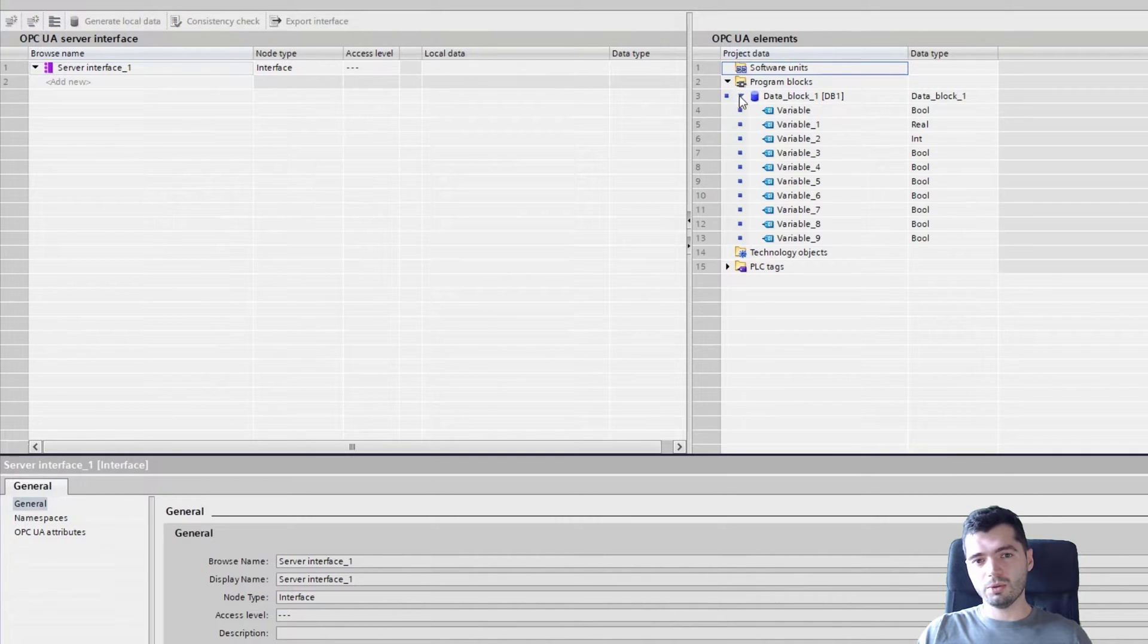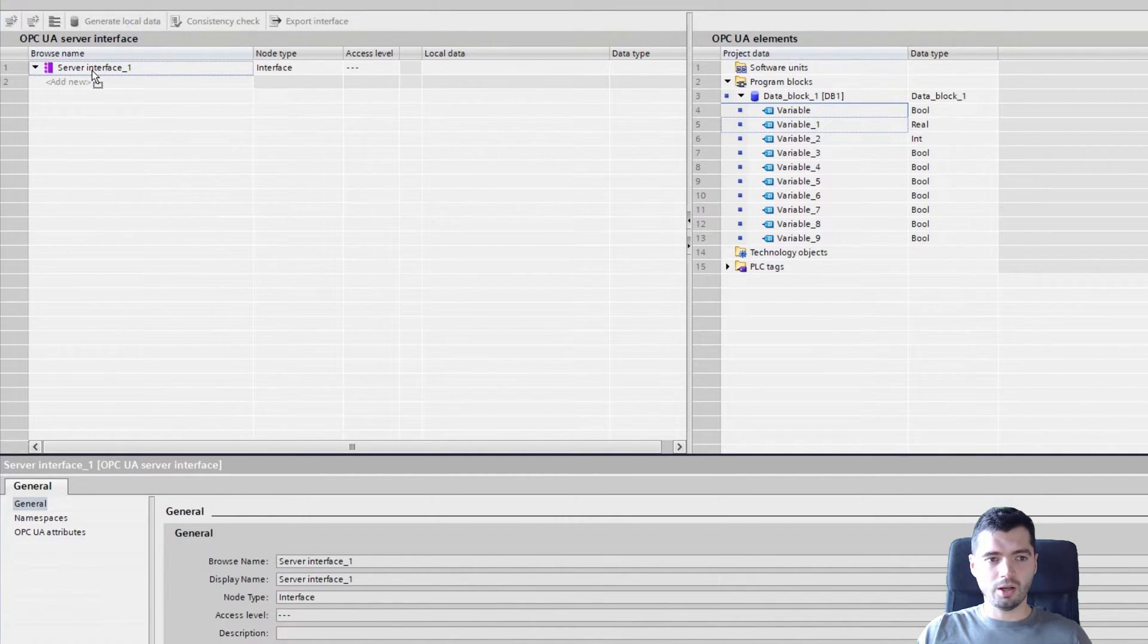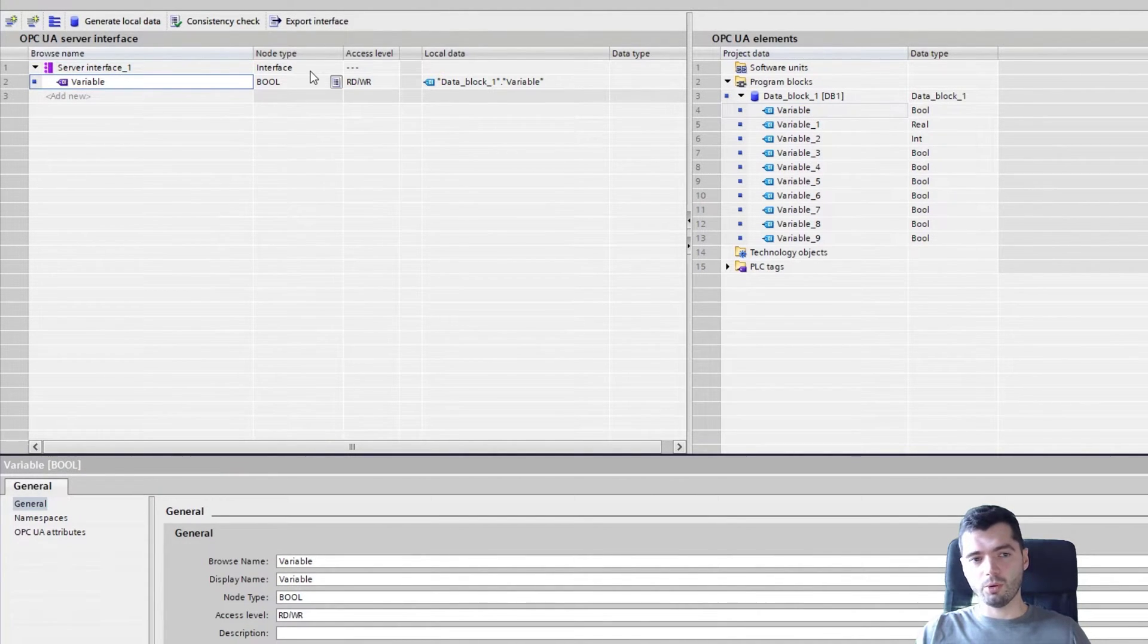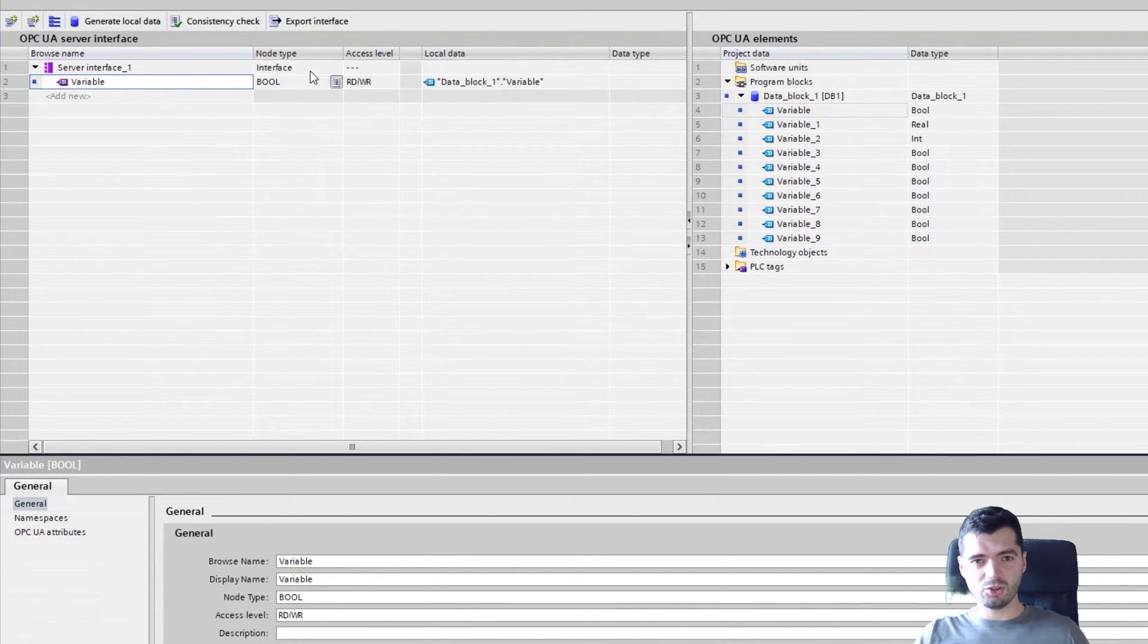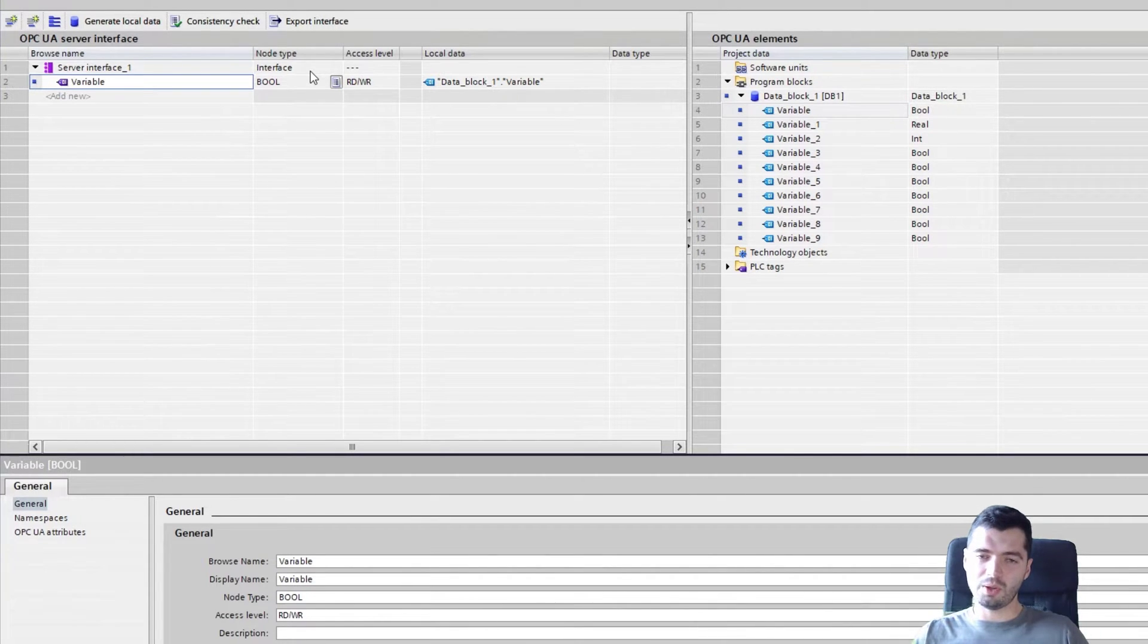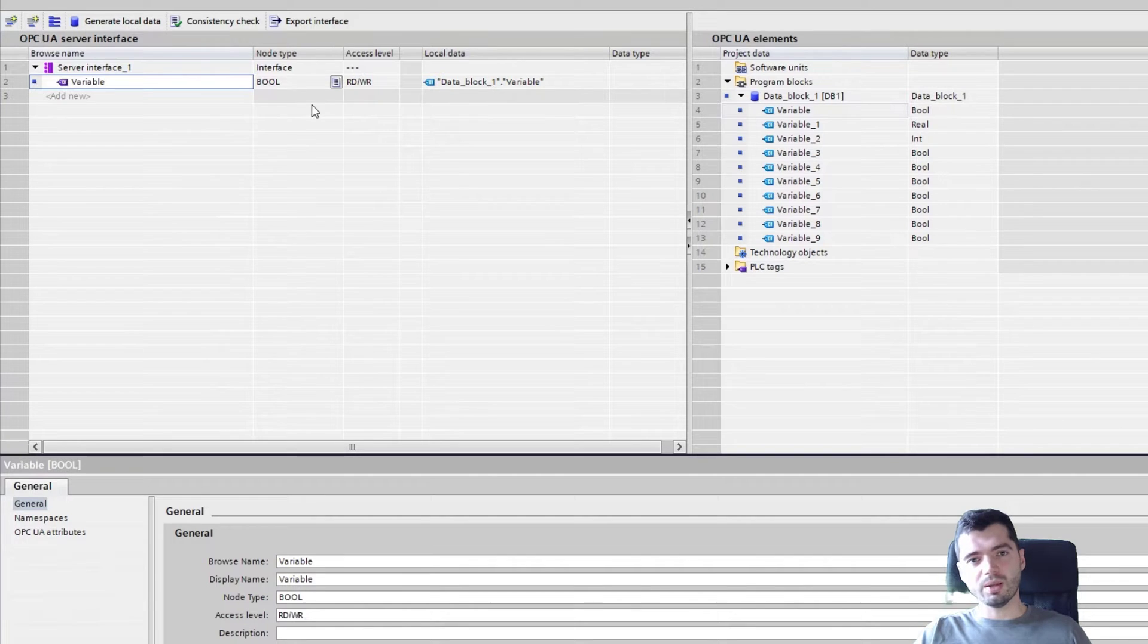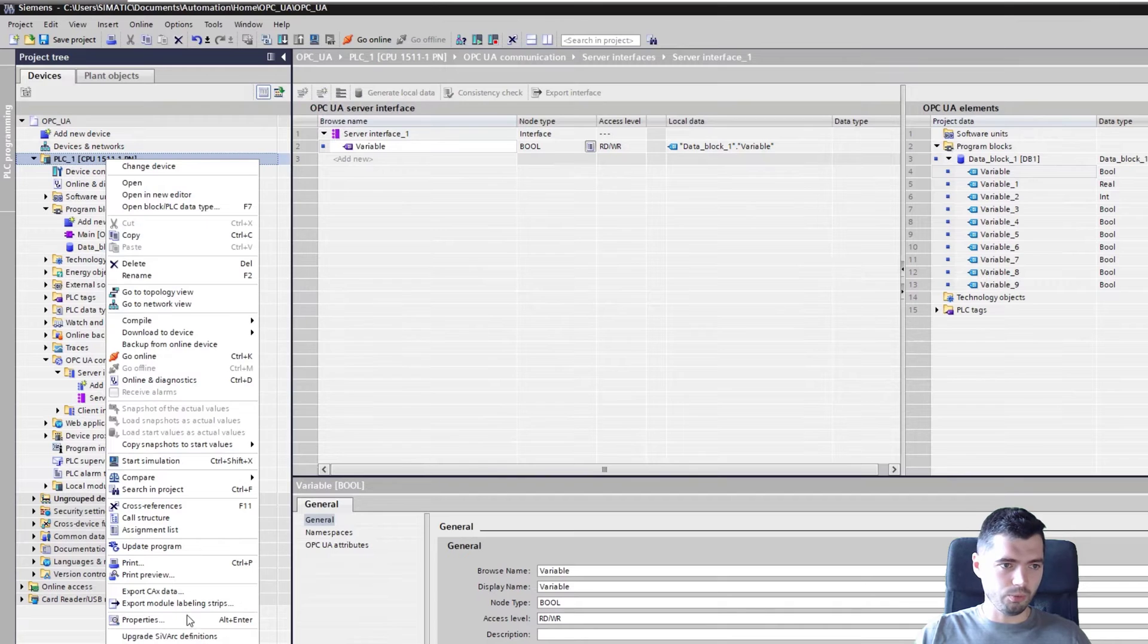And basically what you can do is you can just drag and drop some variables here. And now this variable will be exposed under this server interface. As you may have noticed, I left the standard semantic namespace checked. So if I leave it like this, I should have two namespaces: namespace 3 and this custom namespace, my custom server interface. So we should be able to actually see both.